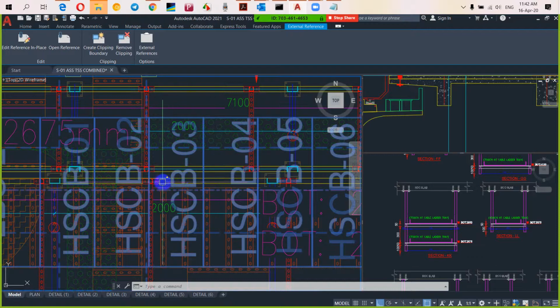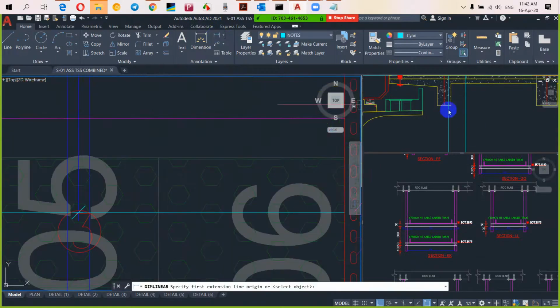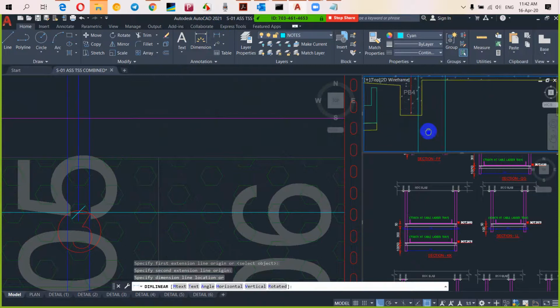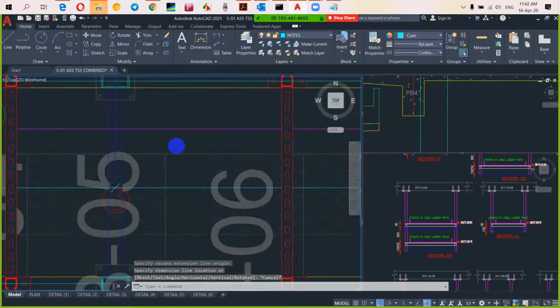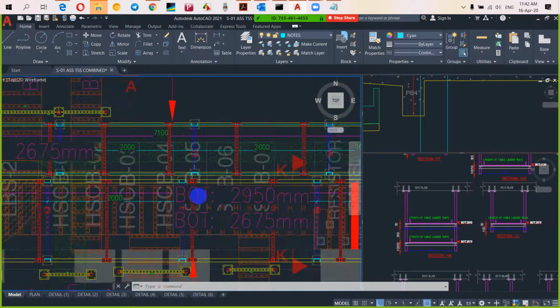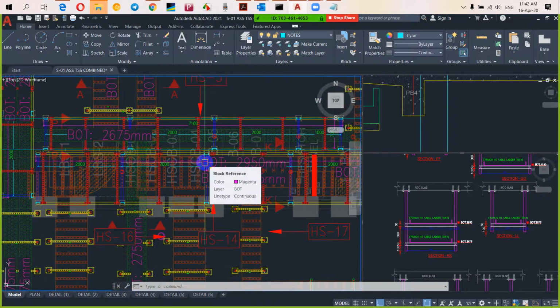Is it required? Because on the support I'm seeing there is a gap. Let me measure how much it is. I'm seeing something like 100 mm space between the tray and the edge of the support. So you can retain the tray in the same position and move it by, okay, you want 200 mm, so 50 mm will be moved. Maybe 100 mm. Ultimately the tray will be positioned 50 mm away from the panel. Is it okay, Rakesh? Yes, no issue. 50 mm is okay for you, so that they can move the support by 200 mm. Yeah, ultimately 200 mm, okay.